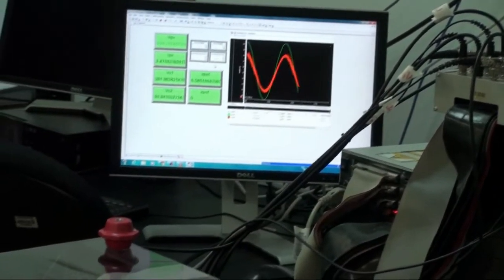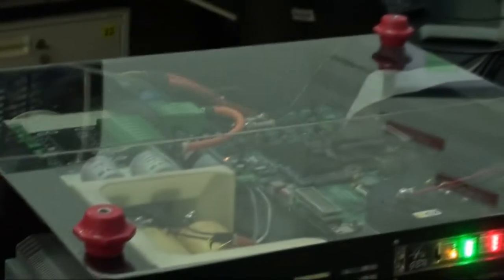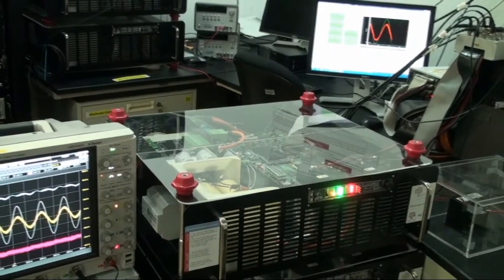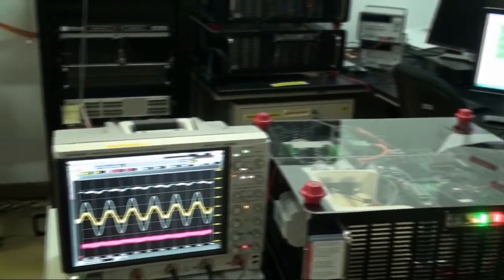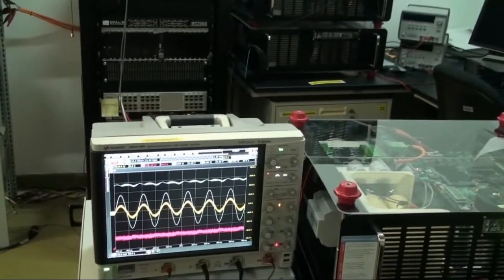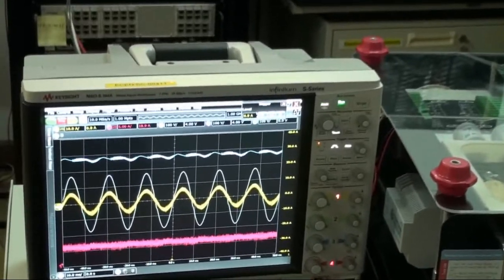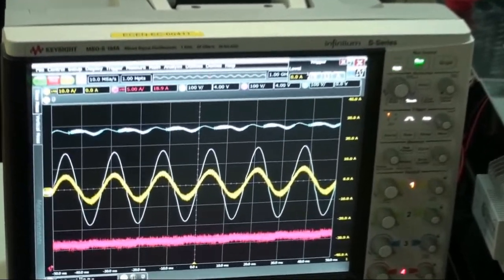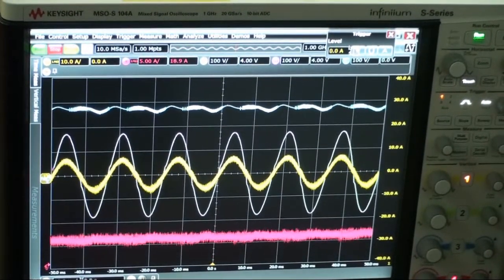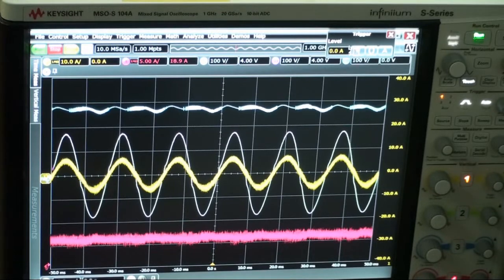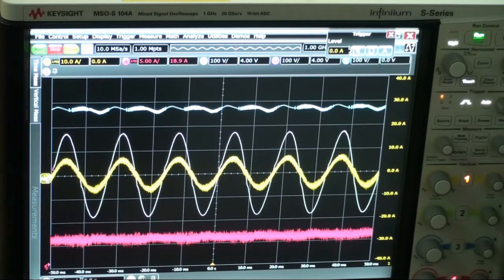In this video, I demonstrate the controller's ability to seamlessly transition into low-voltage ride-through mode, where the controller senses a voltage sag and injects reactive power. Currently, the system is in maximum power point tracking mode, with the capacitor one voltage regulated at 275 volts. In the oscilloscope, the yellow signal is injected grid current. The light green signal in phase alignment with the grid current is the grid voltage. The light blue signal is capacitor one voltage, and the red signal is the input current to the quasi-Z-source module.